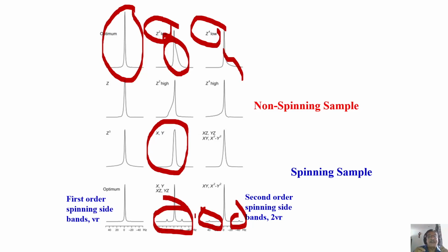As a consequence, you are creating counteracting gradient fields to cancel out the imperfections or inhomogeneities which are inherently present. These are things which you have to practice, and it is not an easy job. And finally, when you are expert, when you do all those manipulations, you will get an extremely good homogeneous field, and lines will be very, very sharp. Not only sharp, the line shape has to be very good.